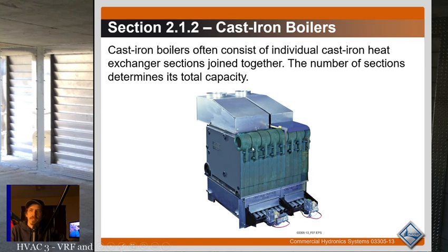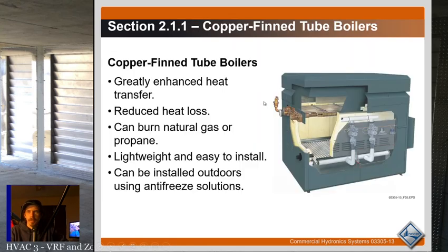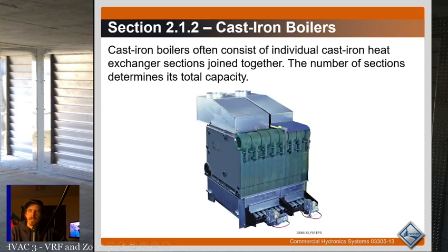So if it cracks, you can pull these bolts off, pull this thing apart, and replace the gasket material that's in between them, usually a type of rope. I forget what it is, but anyway, it's that rope. Then put that back together, bolt it back up, make sure it's torqued to spec, and you can fix just that section. So on big boilers, you'll do things like that. Otherwise, you'll be replacing it. But that's a nice thing.